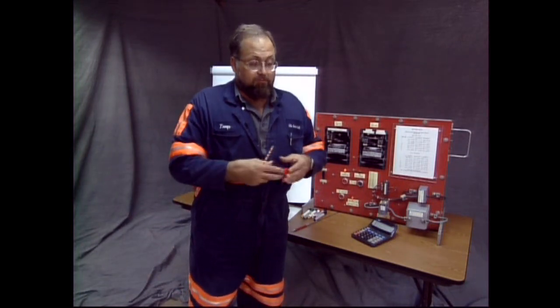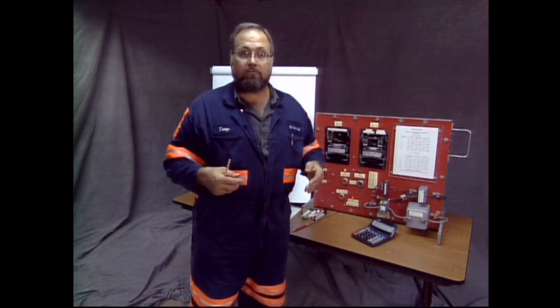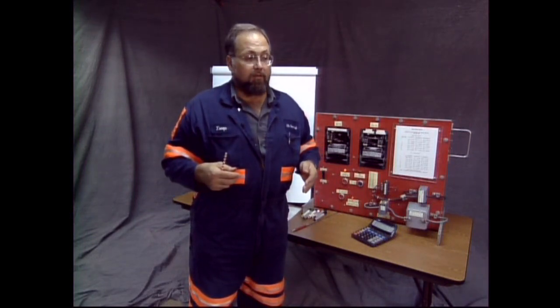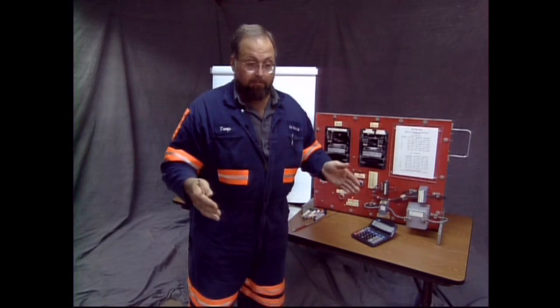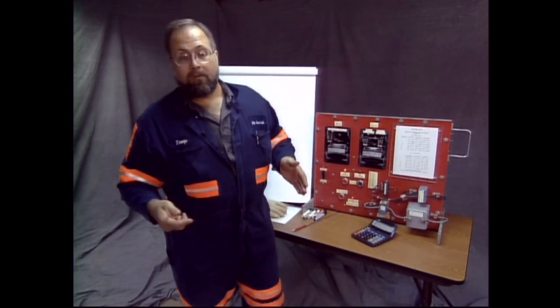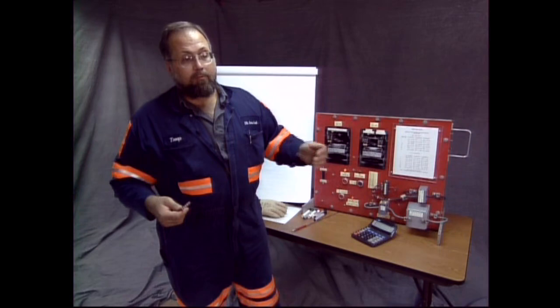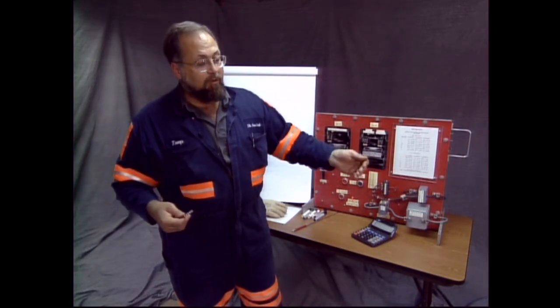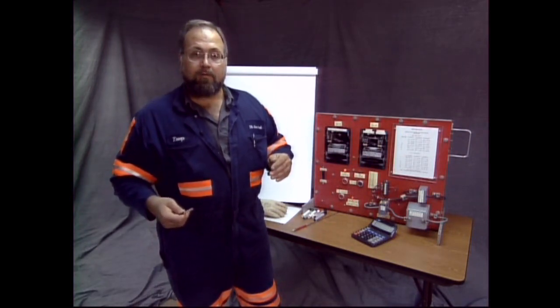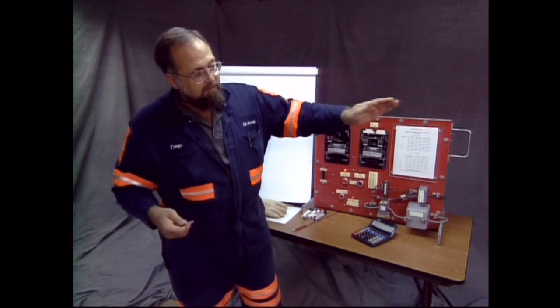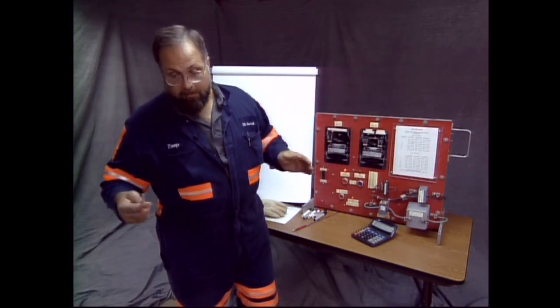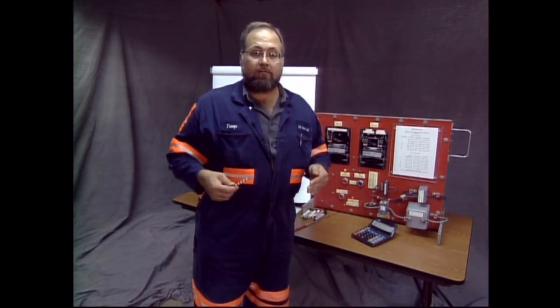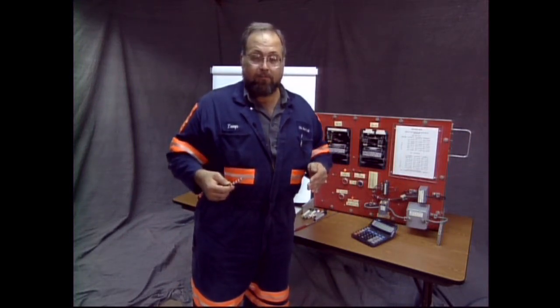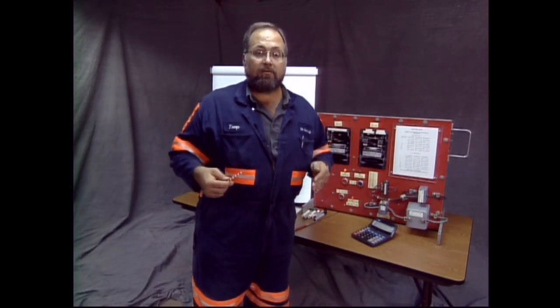The vacuum breaker, the contacts they're in bottles, that they're not visible. An oil circuit breaker, the contacts are in a tub of oil. They're not visible. You have to open a visual disconnect. A gang-operated air break is the most common thing. You're going to open a visible disconnect and actually see the contacts come apart. The next thing, lock and tag. Lock and tag, lock and tag. If you lock this out and you tag it, you take the key with you, and you personally do this, then you know the power is disconnected.